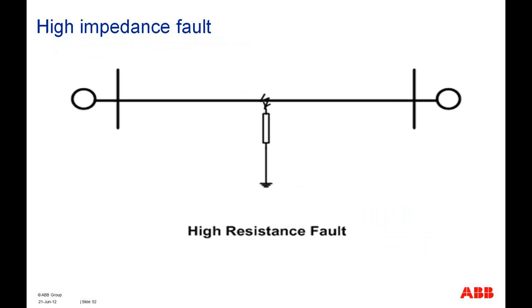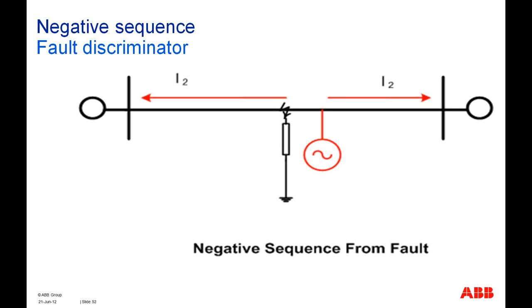High impedance faults are also one of the things which are very difficult to detect, because the ground fault currents are very low. But as we know, numerical relays can calculate the negative sequence current, so we can use that feature to detect those high resistive faults and take care of them effectively. As you can see over here, if a high resistive fault is at this point, it will act as a negative sequence source and the currents will flow out of this fault point.